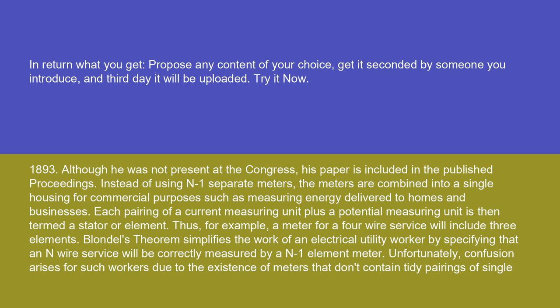Instead of using N separate watt meters, the meters are combined into a single housing for commercial purposes, such as measuring energy delivered to homes and businesses. Each pairing of a current measuring unit plus a potential measuring unit is then termed a stator or element. Thus, for example, a meter for a four-wire service will include three elements. Blondel's theorem simplifies the work of an electrical utility worker by specifying that an N-wire service will be correctly measured by an N-minus-one-element meter.